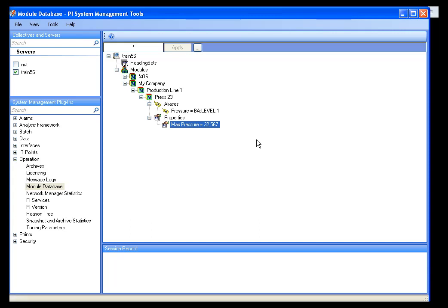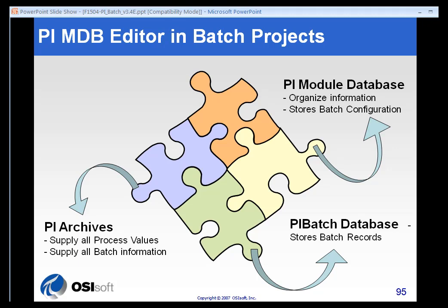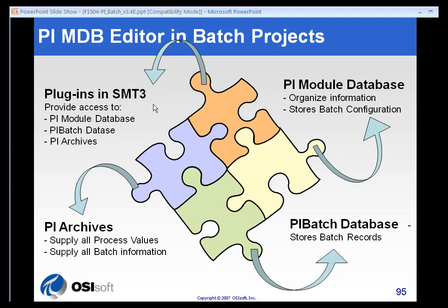So the module database editor is generally what we will use to create modules, aliases, and properties. With this last piece of information, we can fill in the label on the final point of our jigsaw puzzle. We started with the PI archives, which store the process values and batch information. The PI batch database stores all of the batch records — it is what we query to find batches that ran during a certain start and end time or against a certain product or recipe. The module database organizes our process and stores all of the batch configuration information. Finally, our plugins to SMT — the module database editor, a batch database plugin, and a PI archive plugin — all fit together and form the batch system within PI.